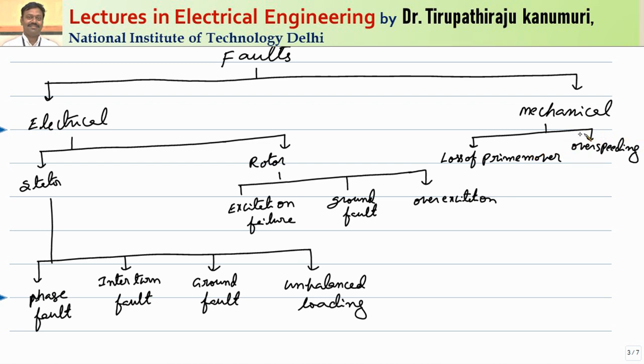The second mechanical problem is over-speeding, which generally happens when the load is suddenly removed or the input to the prime mover is suddenly increased. In that case, the output voltage increases and the frequency will also increase. Since alternator stability is a concern, the frequency should be within limit. Coming to the electrical faults, they can happen either in the stator or in the rotor.